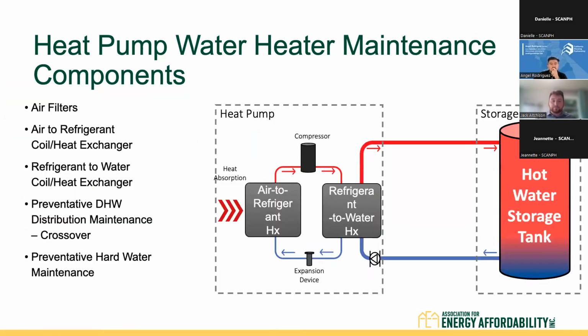Next slide. So heat pump water heater maintenance components. We have air filters again. We're protecting those coils. We have air to refrigerant coil heat exchangers. We have refrigerant to water coil heat exchangers. We also have a little bit different topics than the HVAC, which is preventative DHW distribution maintenance, specifically crossover, and then preventative hard water maintenance. Honestly, the distribution maintenance is very similar to ductwork. That would be the equivalent: making sure that you're either distributing conditioned air or distributing hot water efficiently is going to keep your water heating system operating efficiently.